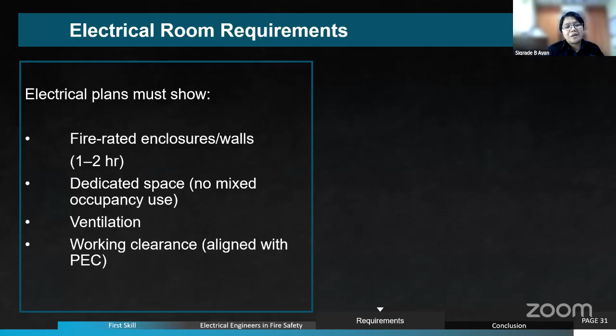So what should we see sa ating mga electrical rooms in our electrical plans? Ano dapat yung makita natin? Una yung sinabi nga natin na 1 to 2 hours fire-rated enclosure or walls. Dedicated space dapat siya, no mixed occupancy used. If it's really an electrical room, it should be electrical room. And proper ventilation. Then the working clearance aligned with the PEC. Ano ba yung proper headroom natin? Ano ba yung proper depth and width natin? It should be in accordance with the Philippine Electrical Code.